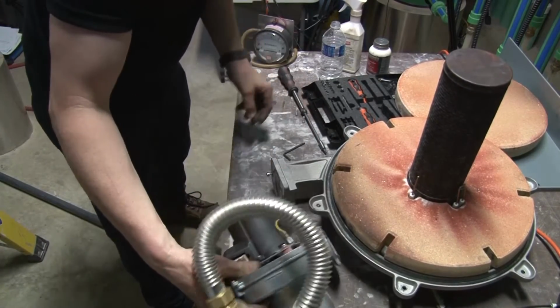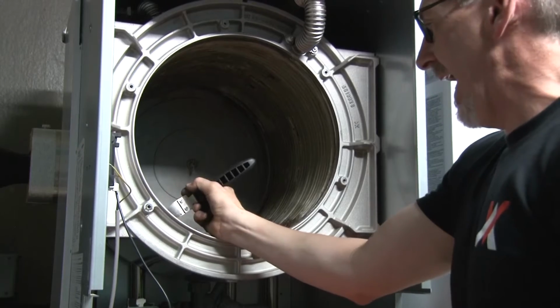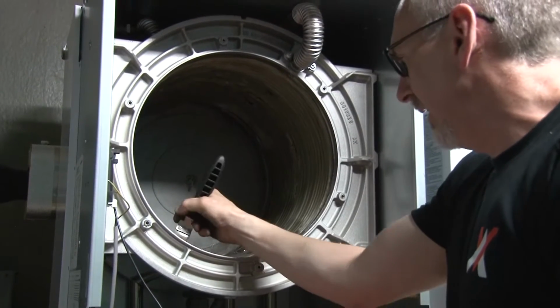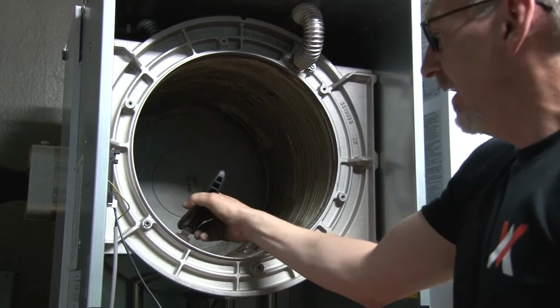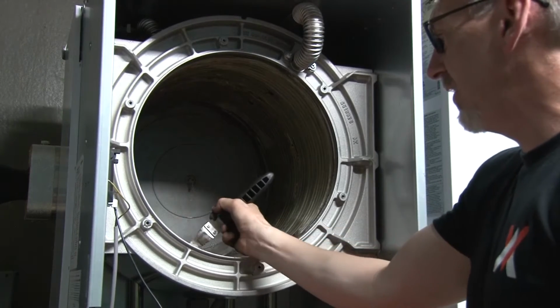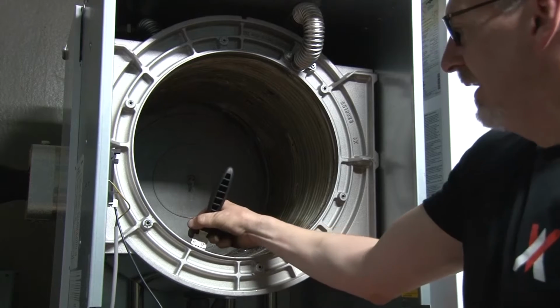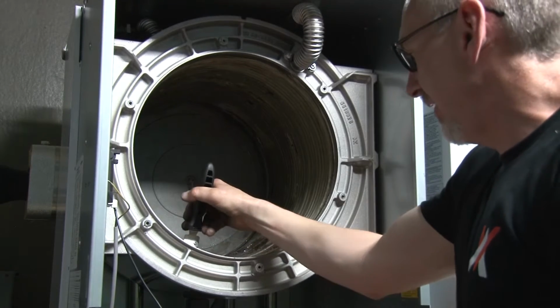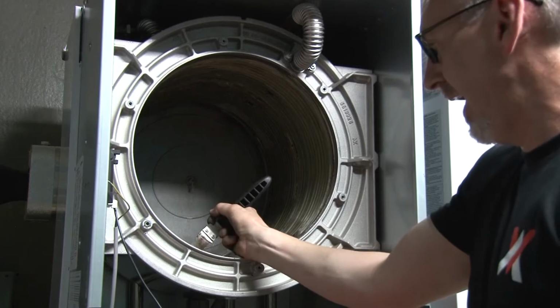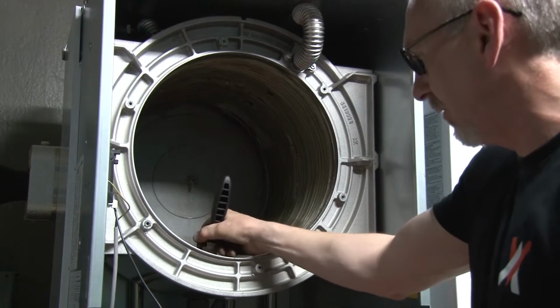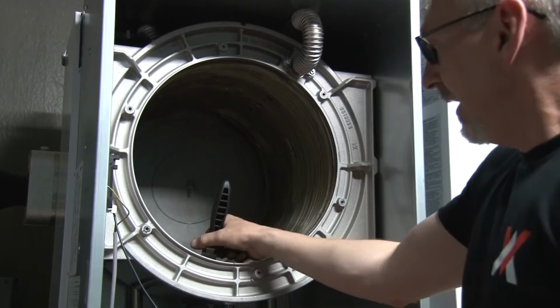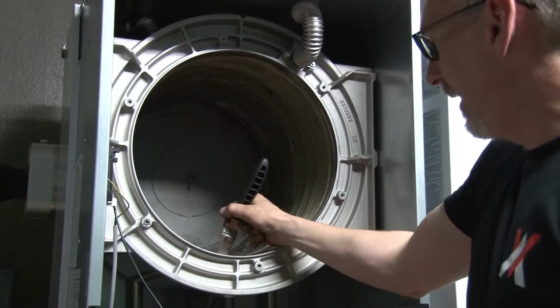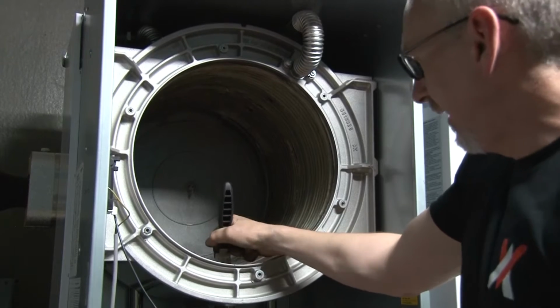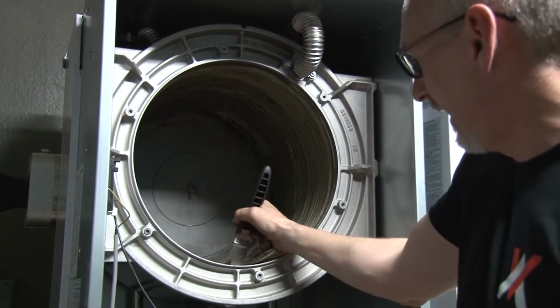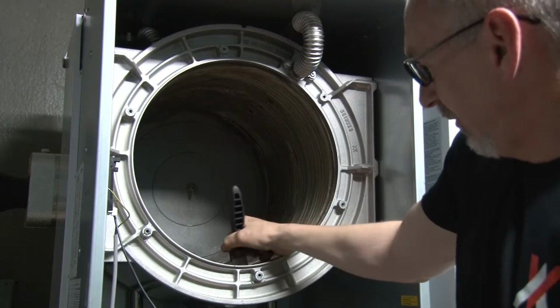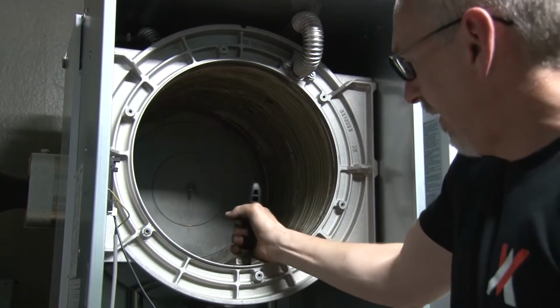So let me perk this up a little bit. We are really adamant in the manuals about not using metal brushes and stuff like that in these stainless steel heat exchangers, because they can cause corrosion. You don't want to gouge the heat exchanger with this knife either, but the idea there is to get these gaps open. So the goal is to have that, basically, so that it cleans that full passageway. And you can see as we work this, as it's been soaked in chemical for a little bit, it's gotten pretty soft, and I can work that down pretty effectively.